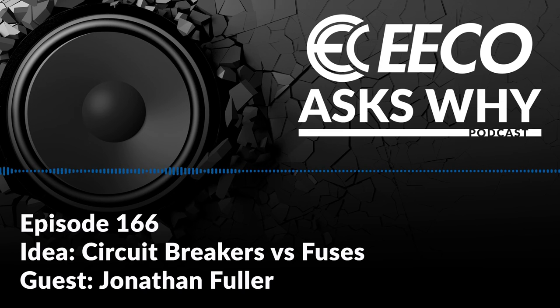That label that you were just referring to, where was that at again? It was actually in the control cabinet where the fuse was mounted. They just took a label maker and made a little label that said class RK5 5-amp fuse only and stuck it right there on that panel. So that way when they're looking in there at that blown fuse and pulling it out, there's no question of what's supposed to be there. Wow, that's a really great best practice. I hadn't really seen that to that degree. Thank you for sharing that, Jonathan.